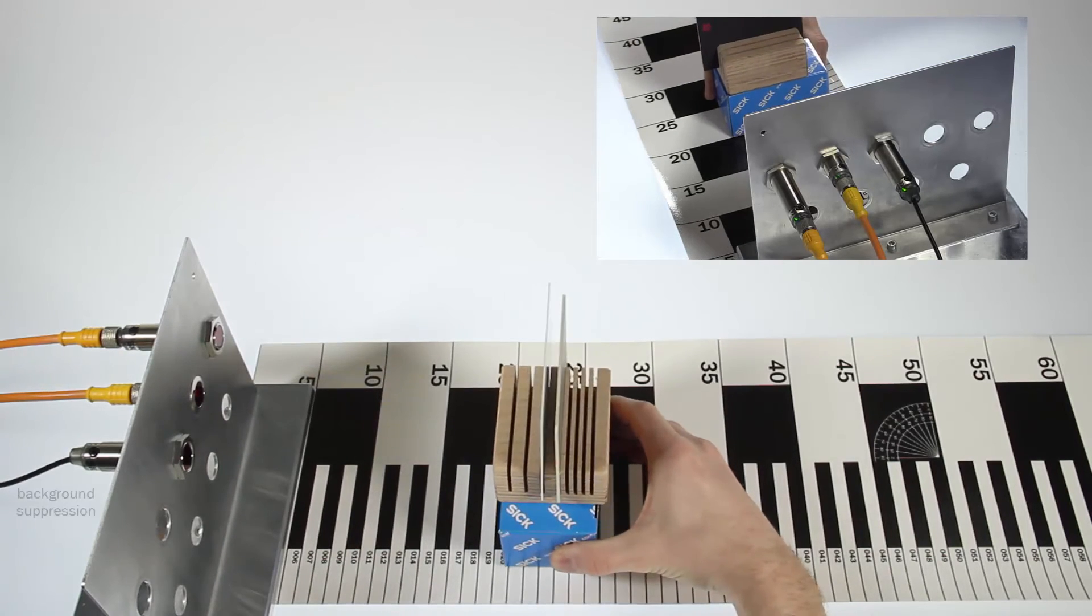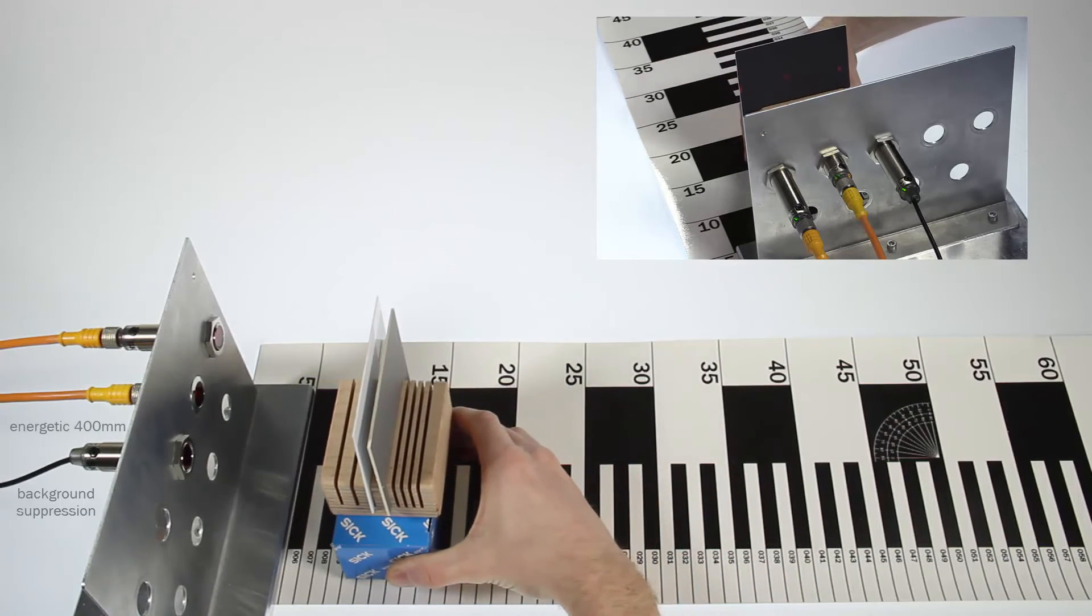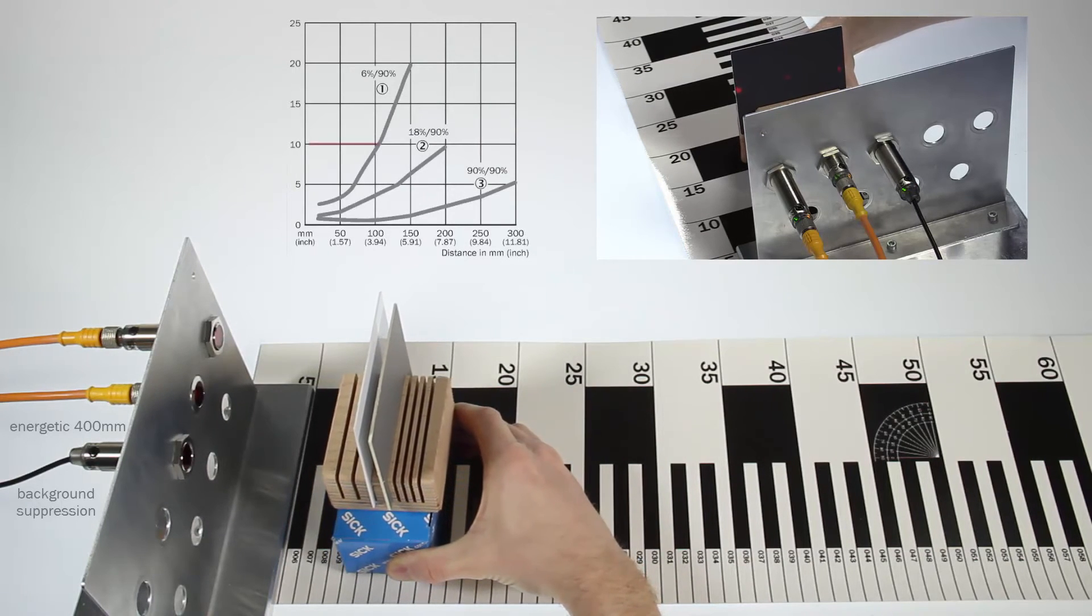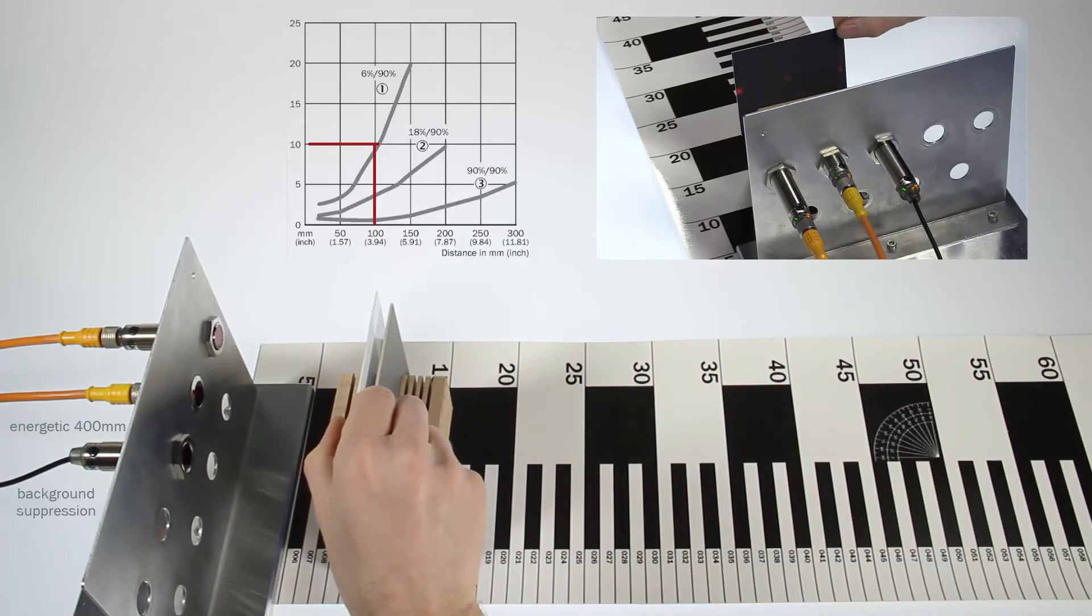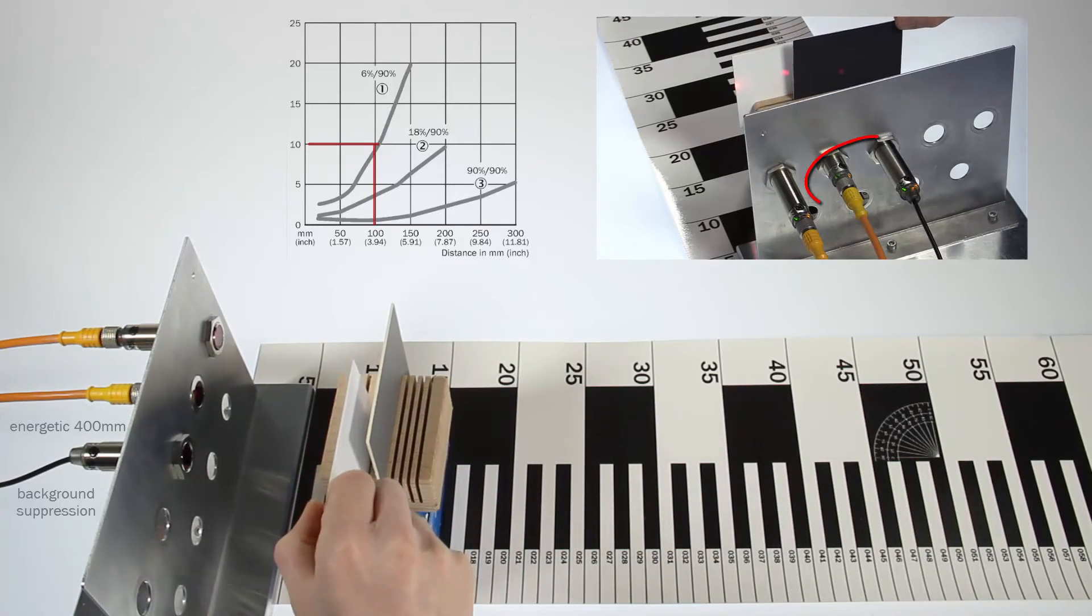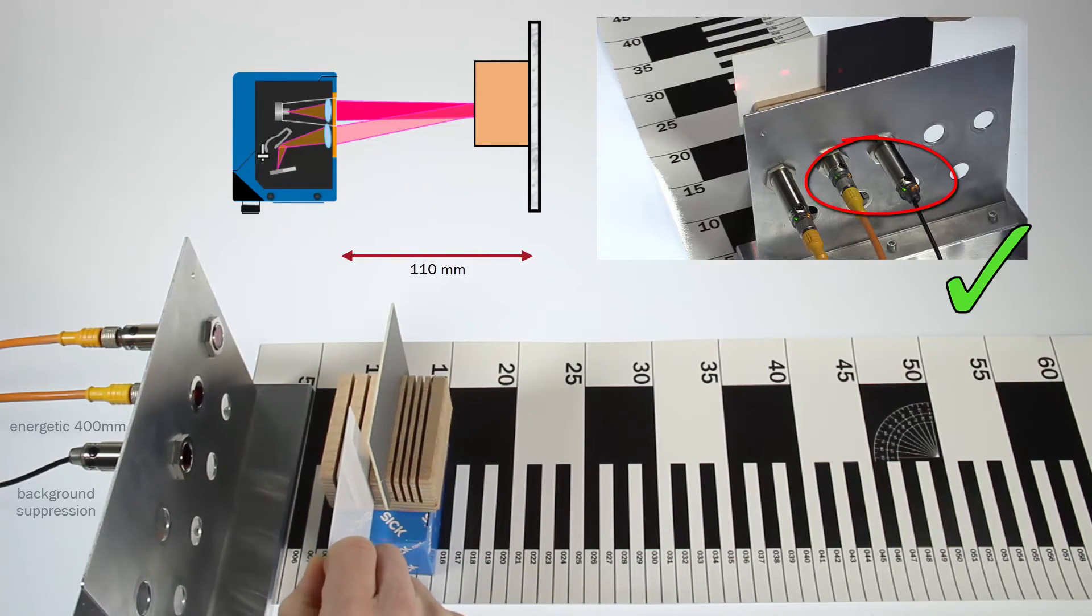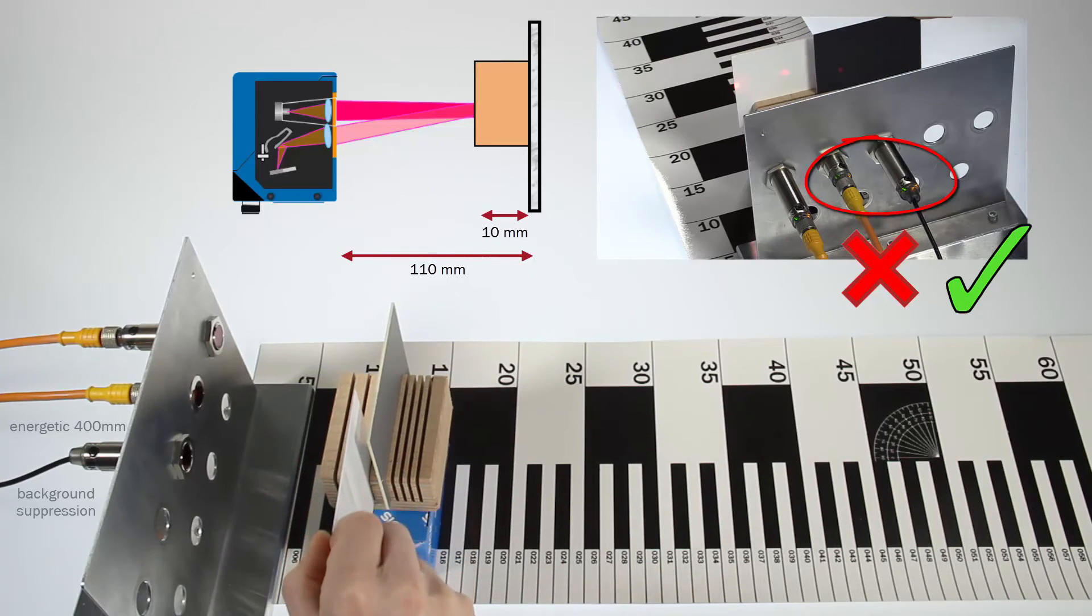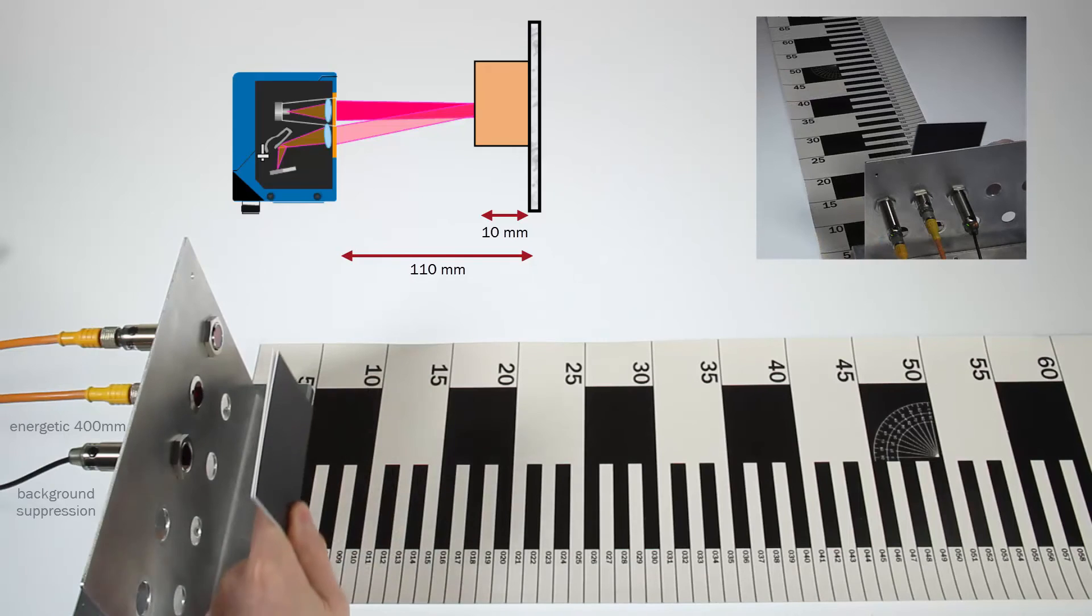Comparing the background suppression version with the 400 mm energetic version, we will have the following situation. The background suppression version is able to suppress the white background with a height of 10 mm at a sensing range of 100 mm, which means the sensor is able to suppress the background after 110 mm, which is just the same as a minimum object height of 10 mm or a difference between object and background of at least 10 mm.